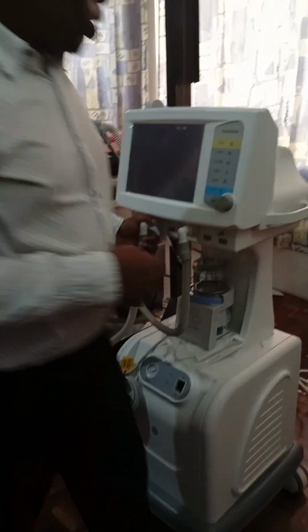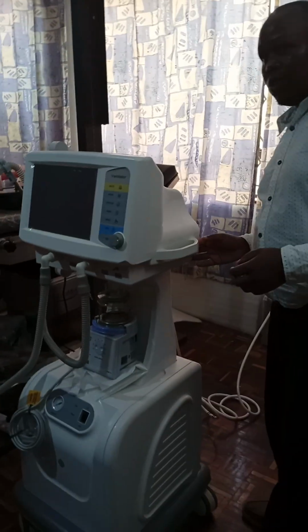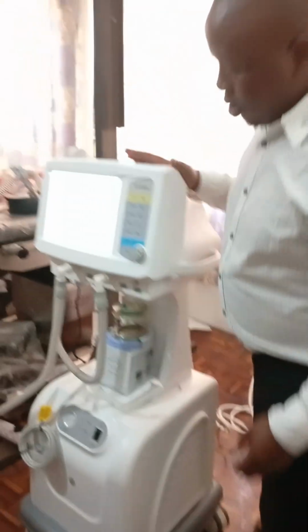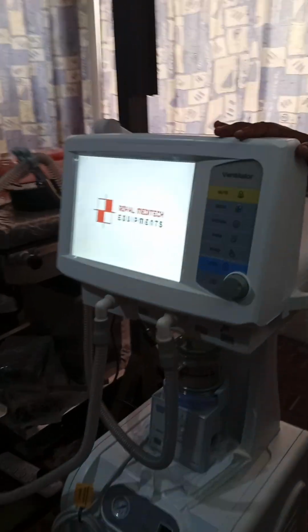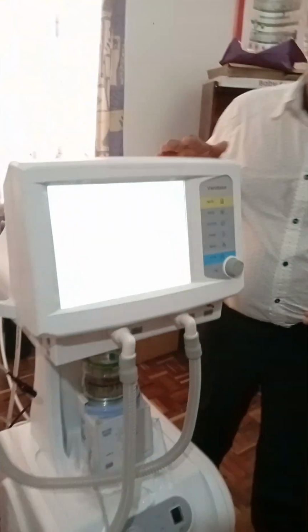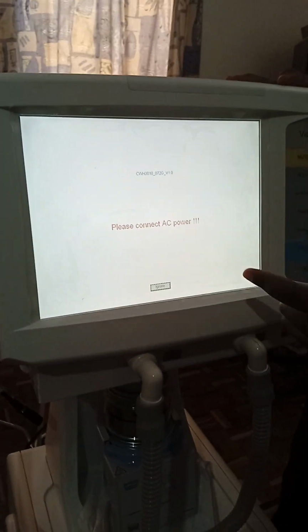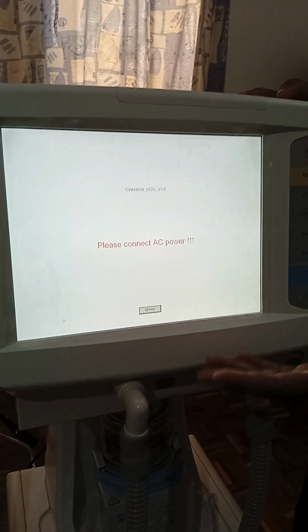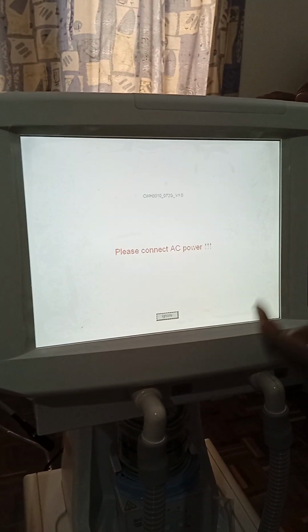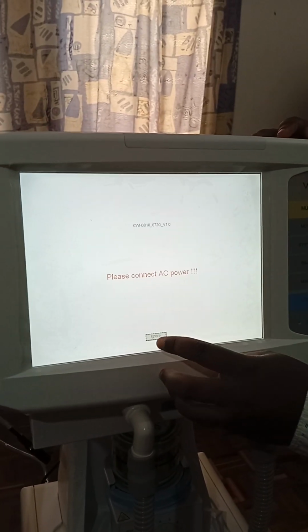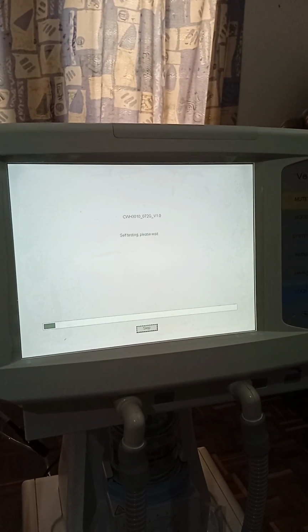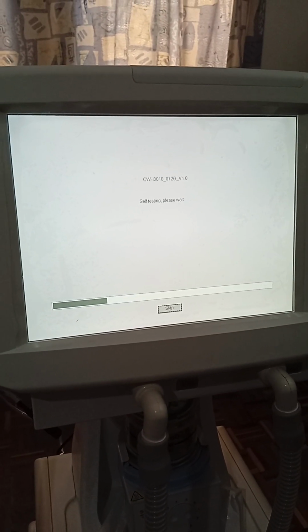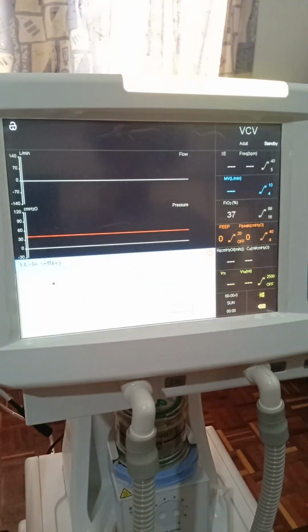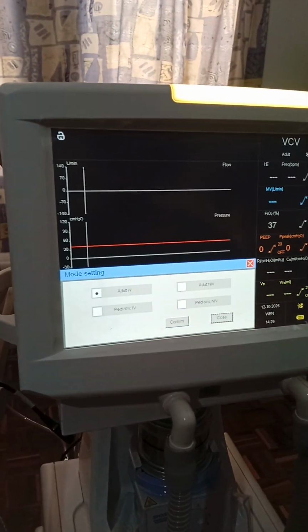Now we are going to switch on the machine and then I'll take you through the operations. As I've told you, this machine you can use either with oxygen or with medical air. When you are switching on the machine, if the battery is low, it will give you a warning here to connect the AC power, and you can ignore that one. When the machine is switching itself on, it does the system checks on its own. In case there is an issue, it will be able to tell you.